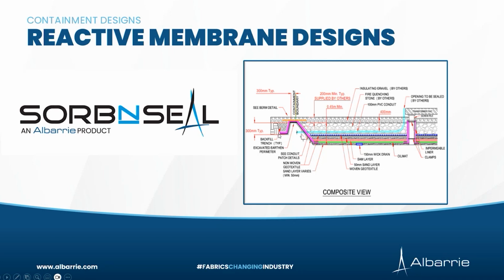That berm is then lined with the impermeable liners as well as all the vertical structures, like the piles in this case. That's the pink material or liner you see here, which is impermeable. We put a geogrid over the berm because the berm is the weakest point in the containment, depending on soil bearing capacity and so on. The geogrid provides additional protection over the berm to prevent it from buckling—it's the same material used in road construction. Then we build the containment below grade and fill it with stone. This gives you a containment system designed to be maintenance free, allowing full access to the equipment in a substation without climbing over things, so it doesn't create any barriers for access.